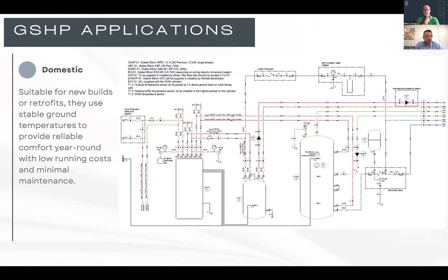And here you've got different applications. I will just quickly go through this. You've probably seen this. You've got a domestic system, and they are all very similar. You've got a heat pump, hot water cylinder, buffer tank. That's the normal setup in the plant room. You've almost always got an additional buffer tank, which stores the heat for the central heating. So that's the setup for a domestic system.